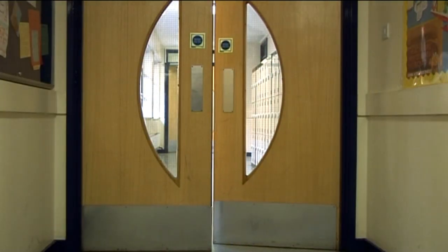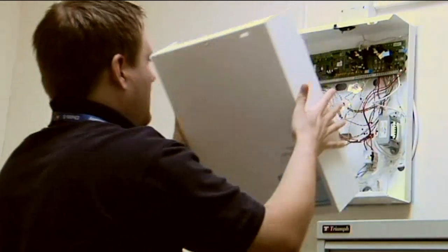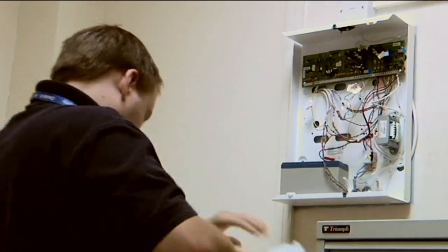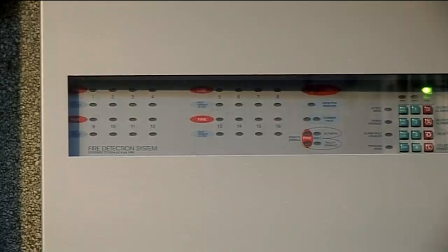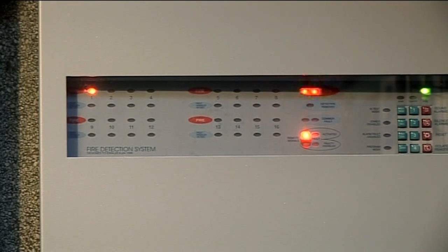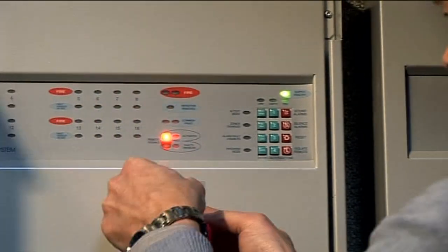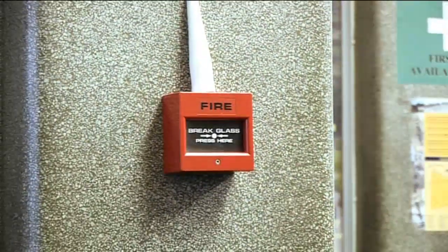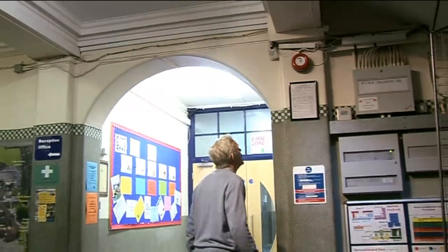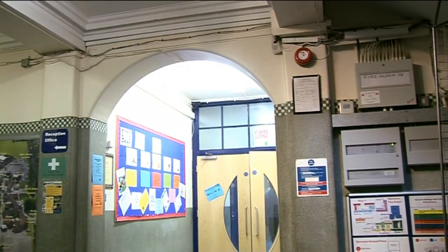Fire safety provisions must be checked regularly and maintained by a competent person, such as a third-party accredited contractor, to ensure that they remain in good working order. The end user should also undertake more frequent regular checks of the system and equipment. For example, the alarm system should be tested on a weekly basis, with different call points being tested in rotation. Records should be kept of these checks. False alarms must also be investigated in full, recorded, and steps taken to ensure they don't happen again.